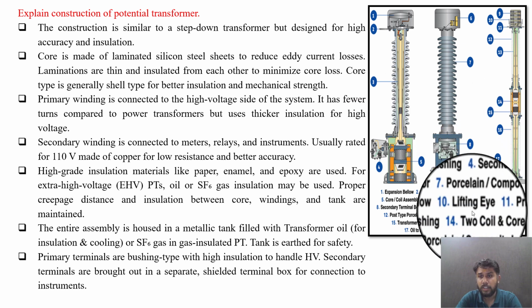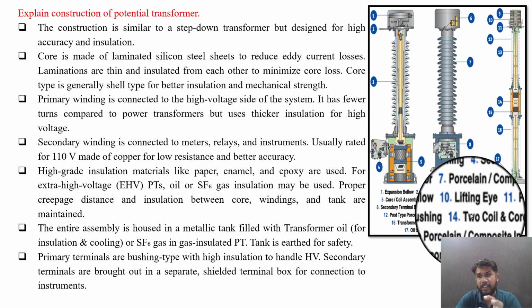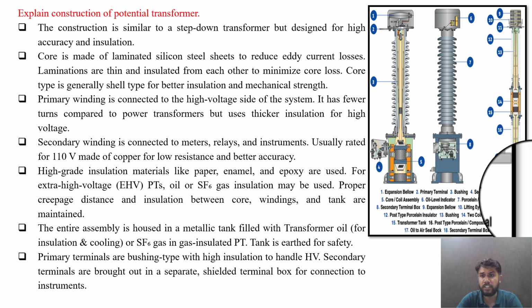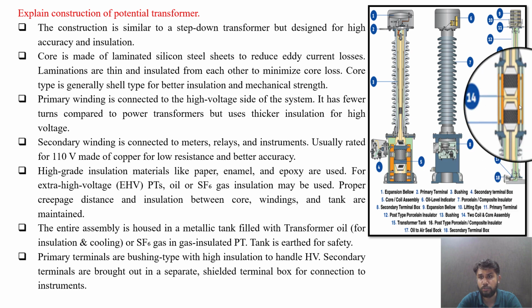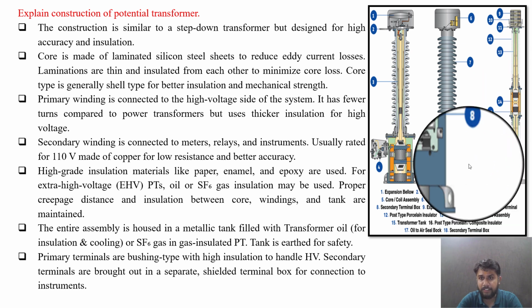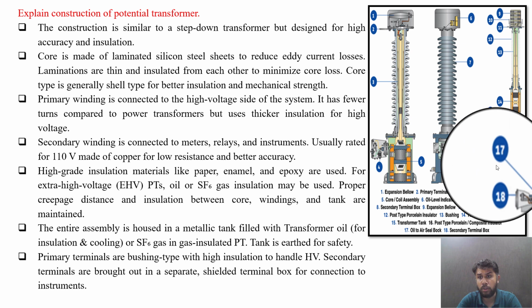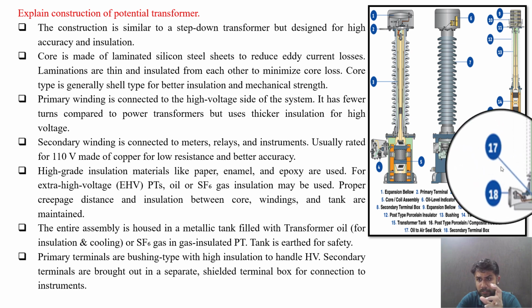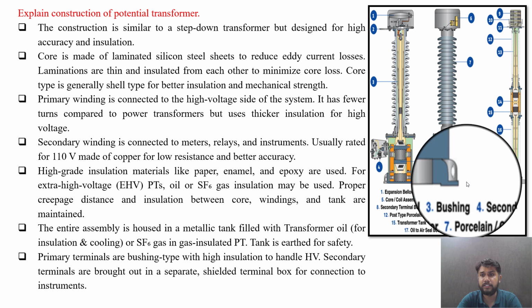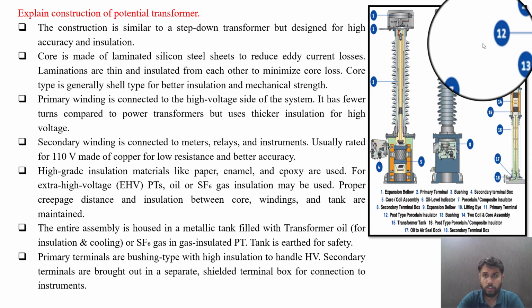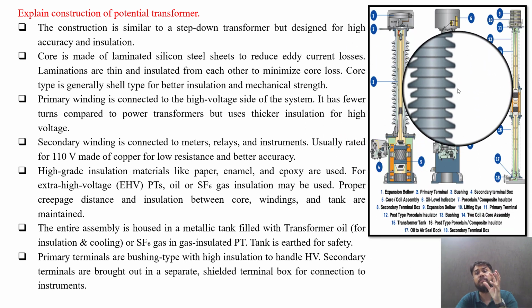15 is the transformer tank, that is the tank of the potential transformer. 16 is the post type porcelain or composite insulator. Here this is 16. 17 is the oil to air seal, where the cock is connected. 18 is the secondary terminal box that is shown. So this is how the number of parts are shown in the figure for the potential transformer, and the construction is very similar to the step down transformer that we have seen till date.